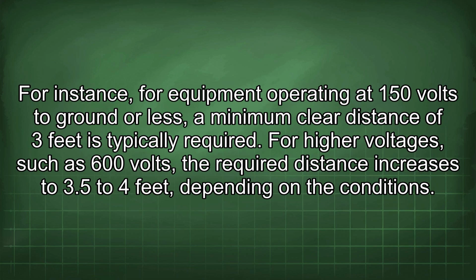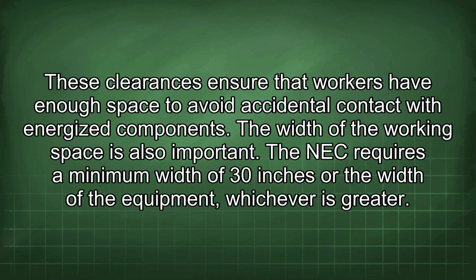For instance, for equipment operating at 150 volts to ground or less, a minimum clear distance of 3 feet is typically required. For higher voltages, such as 600 volts, the required distance increases to 3.5 to 4 feet, depending on the conditions. These clearances ensure that workers have enough space to avoid accidental contact with energized components.